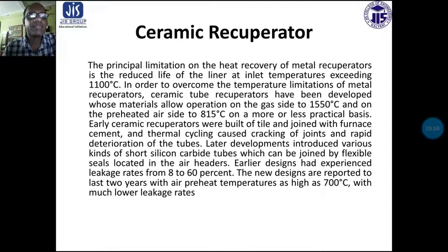Next is the ceramic recuperator. The principal limitation of heat recovery with a metal recuperator is the reduced life of the liner if the inlet temperature exceeds 1100 degrees centigrade. So we cannot use a metallic recuperator where the flue gas temperature exceeds 1100 degrees centigrade.